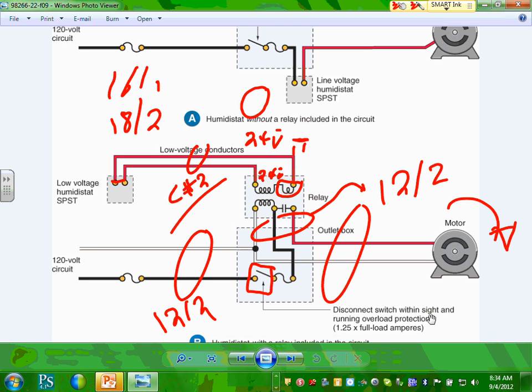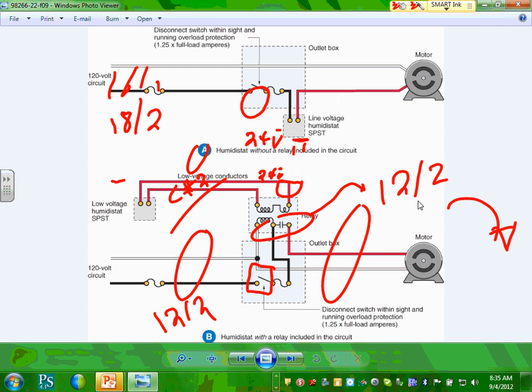In our project, my assumption, guys, is that for the exhaust fan we're going to have a temperature control built in. When you asked me about the controller, I said it's going to have a built-in controller. We're assuming it's going to have a built-in controller with a disconnect right next to it, and it controls itself. For the baseboard heaters, they're also going to have a built-in controller on the side. So all you have to do is provide a 20 amp circuit with 12-2 to it. Any comments, any questions? So that's basically what your controller is going to look like.